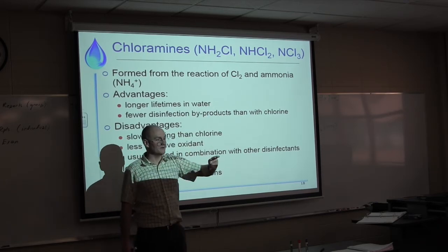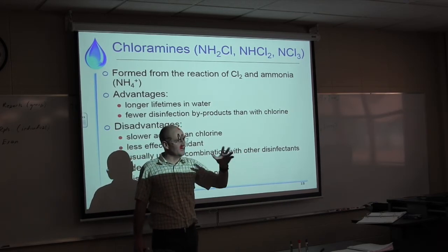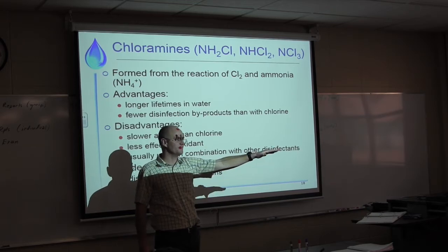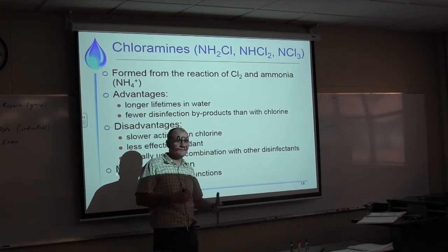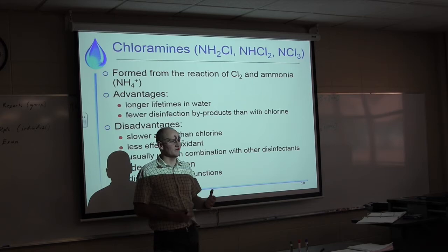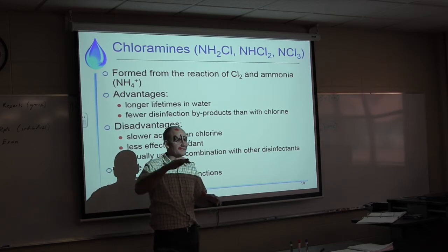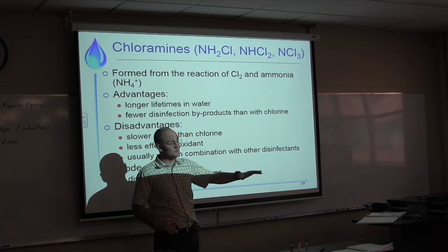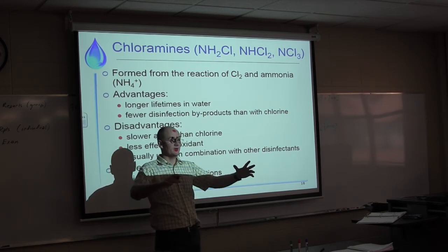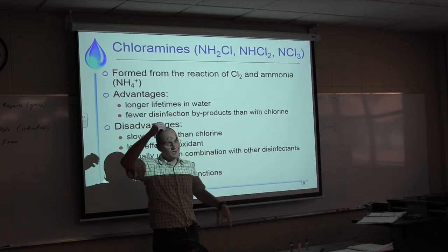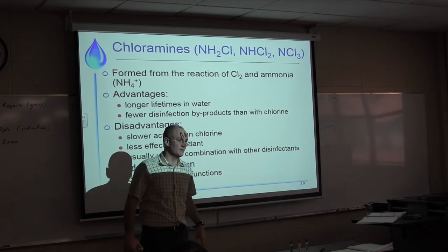So Katie, you mentioned the residual. You needed it to last to your longest customer. Chlorine residuals can go up to a day or so, 20 hours, 24 hours, something like that. Maybe longer if you increase the concentration. But chloramines will last even longer, a couple days. So if you have a huge distribution network, then you might want to use chloramines.